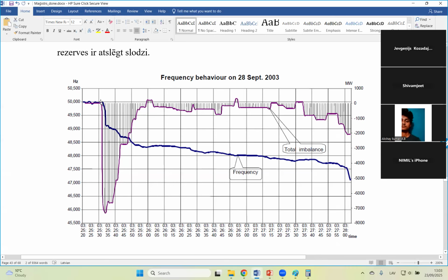Point of disconnection. When we have the imbalance, here is the number of megawatts, and here we have the frequency. So, an imbalance of 7 gigawatts. As a result, we have an immediate frequency drop. What to do? We need to balance the system. The only way is to disconnect the load, and it is described step by step, based on the set point. Start to disconnect the load. And here we can see this is a balance. You see, step by step, start to disconnect the load.